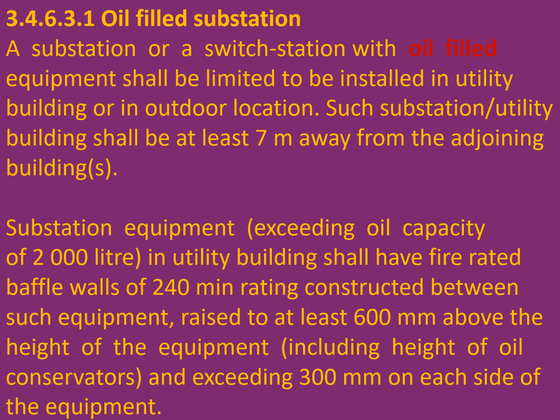Friends, we use the dry type of transformer or oil filled type of transformer substation. A substation or switch station with oil filled equipment, mostly transformer, shall be limited to be installed in utility building or in outdoor location. That means almost prohibited. Such substation or utility building shall be at least 7 meters away from the adjoining buildings. Substation equipment exceeding oil capacity of 2000 liter in utility building shall have fire rated walls of 240 minutes rating. That means 4 hours.